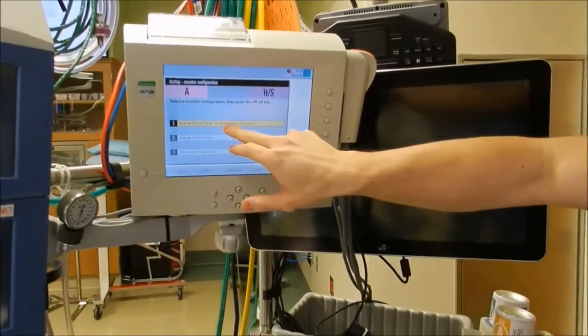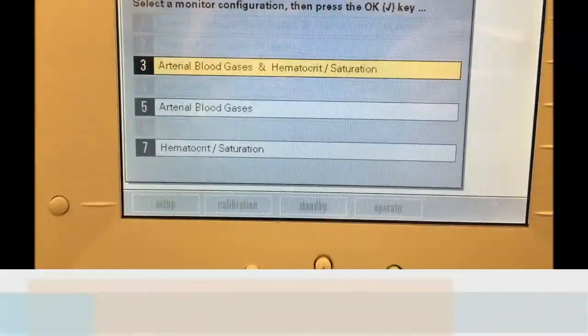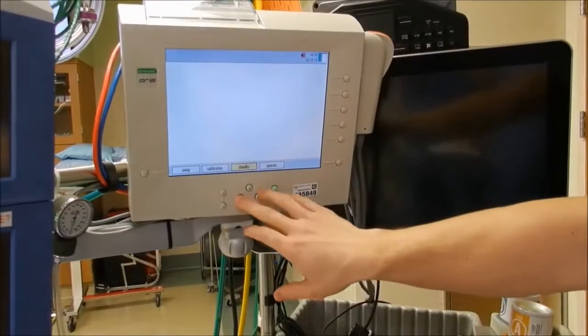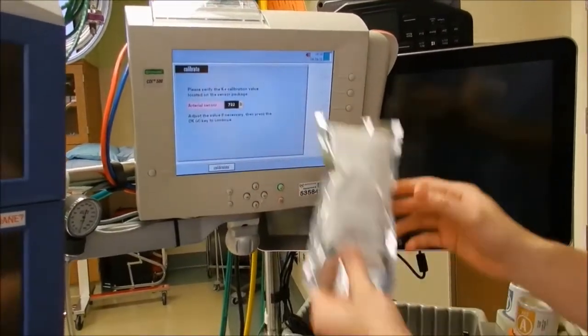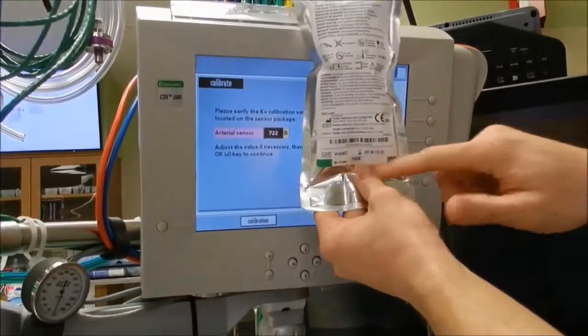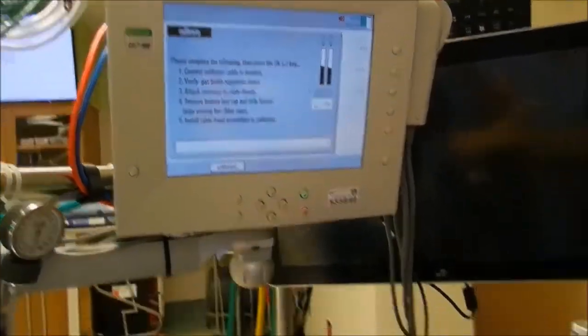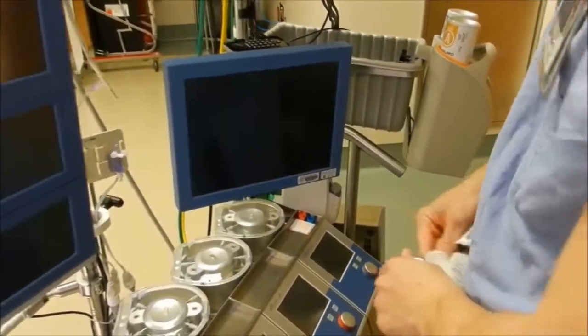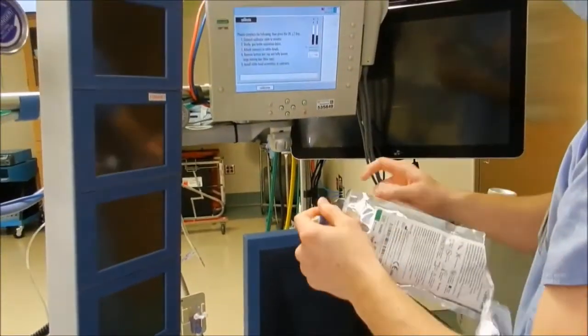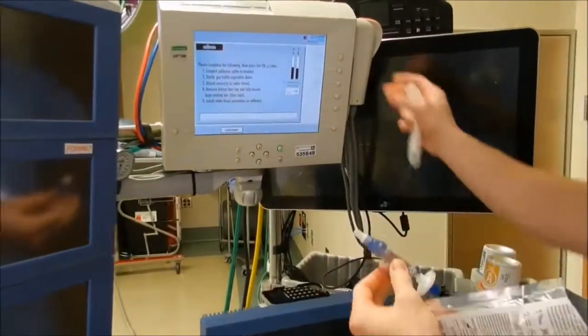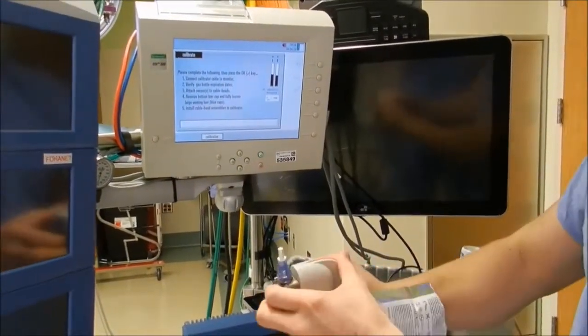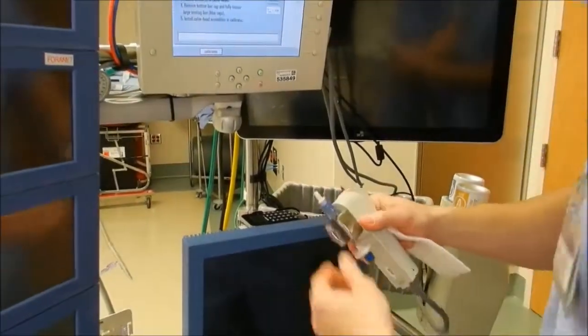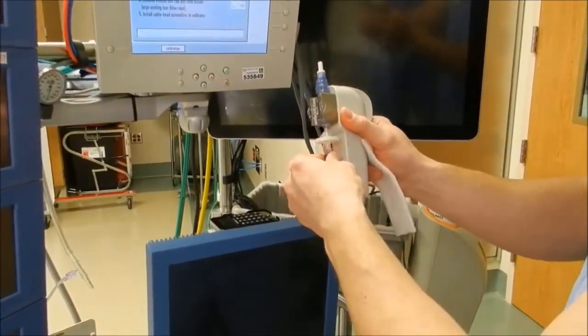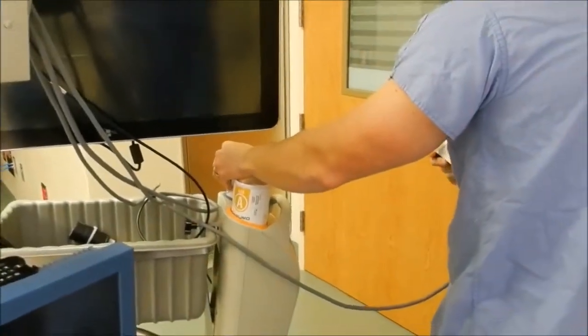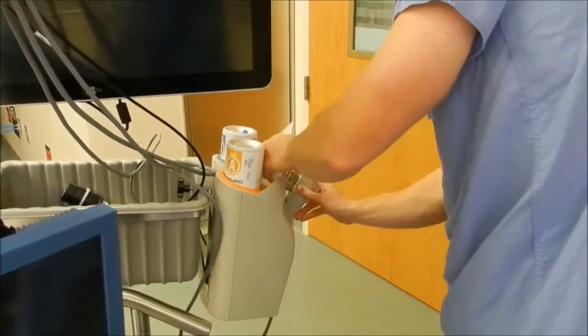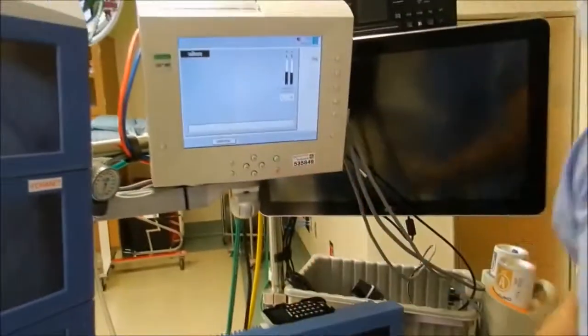We're going to calibrate to our arterial blood gases, hematocrit and saturation. Move over to calibration. Make sure the numbers match, 722B and 722B. Looks good. So we just follow directions as it lays out on the screen. Take our CDI cuvette and the arterial monitor. This clicks into place. You can hear a nice click. Loosen the top. Take the blue cap off the bottom. And we'll go ahead and plug it into the calibrator and get that started.